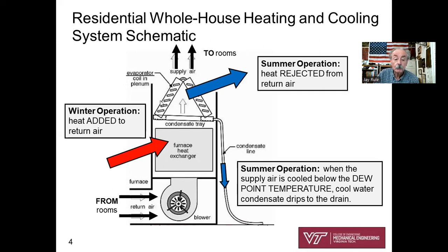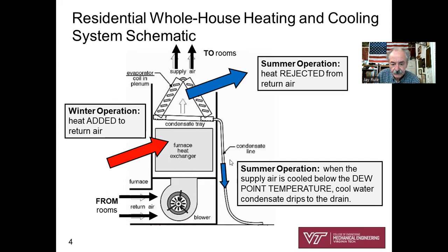In the summertime, we don't use the furnace — we use the evaporator section from a traditional vapor compression refrigeration cycle. These cold coils cool the air. Whether winter or summer, we get comfortable supply air going back to the room. In the summer, the evaporator rejects heat; in the winter, we add heat. In summertime, the evaporator is so cold it cools the flow below the dew point, and you get condensate dripping to the drain.